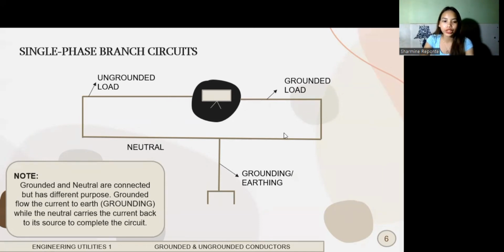Or if there is a fault in the wiring system, the electric current will flow in the grounded conductors to bring the current to the ground. We call this process grounding or earthing. Take note that grounded and neutral conductors are connected but have different purposes. Grounded flows the current to earth, that's what we call grounding, while the neutral carries the current back to its source to complete the circuit.